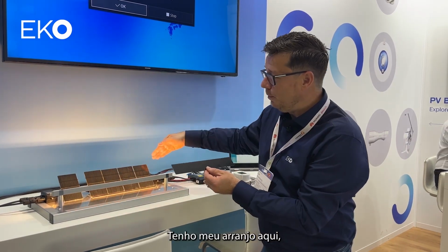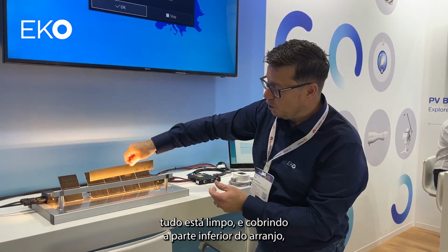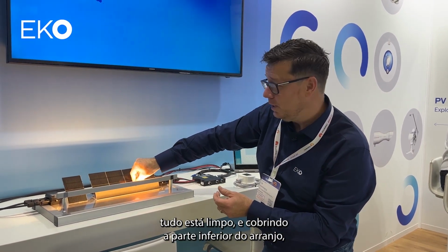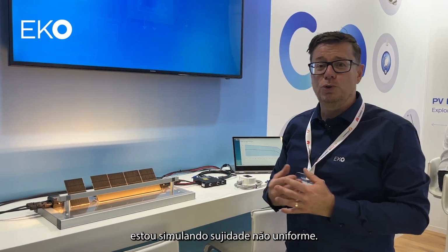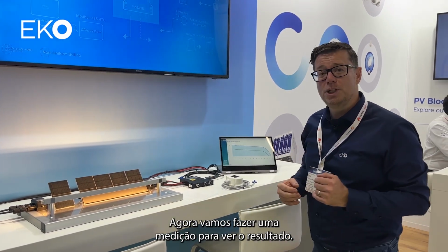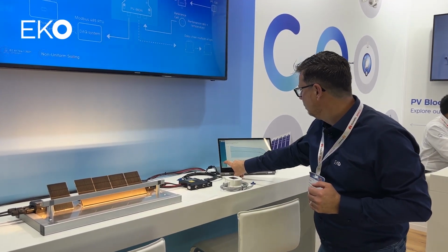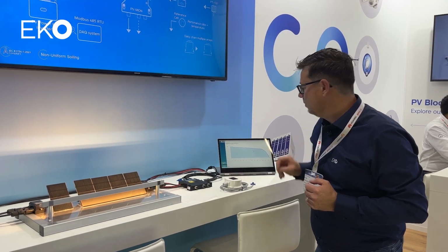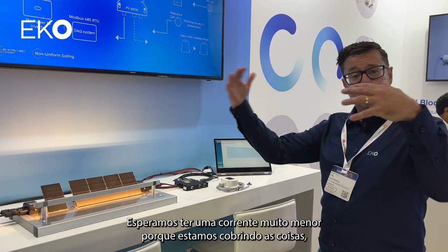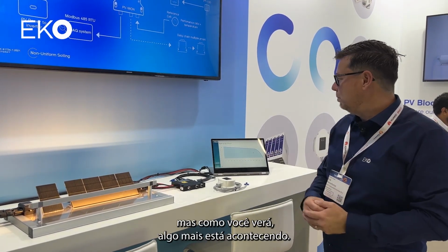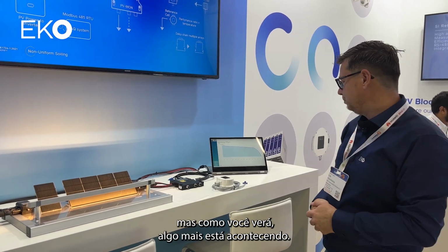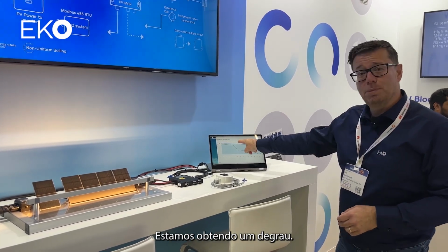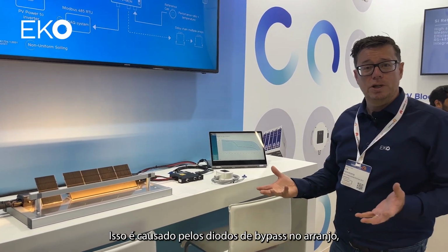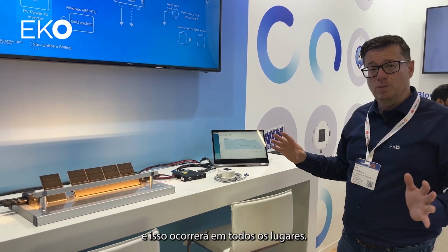I have my array here, everything is clean, and by covering the bottom part of the array, I'm simulating non-uniform soiling. Now let's do a measurement and see what comes out. We expect to have a much lower current because we're covering things, but as you will see, something else is happening. We are getting a step. This is caused by the bypass diodes in the array, and this will be everywhere.